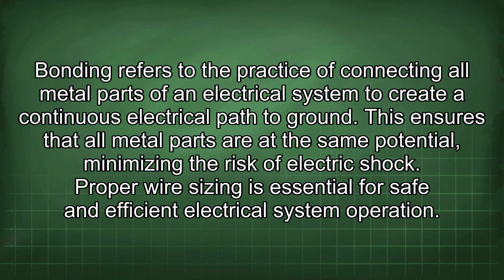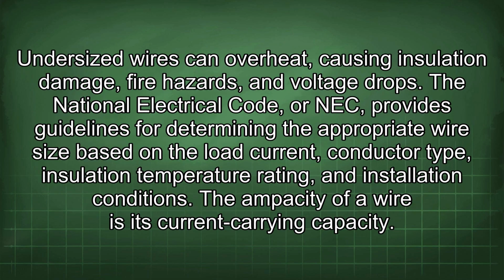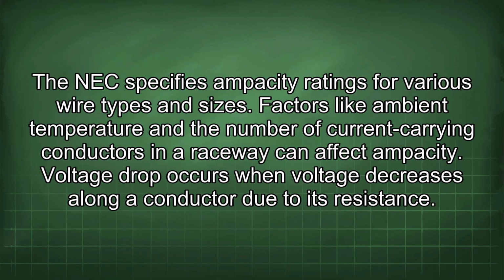Proper wire sizing is essential for safe and efficient electrical system operation. Undersized wires can overheat, causing insulation damage, fire hazards, and voltage drops. The National Electrical Code, or NEC, provides guidelines for determining the appropriate wire size based on the load current, conductor type, insulation temperature rating, and installation conditions. The ampacity of a wire is its current carrying capacity. The NEC specifies ampacity ratings for various wire types and sizes. Factors like ambient temperature and the number of current carrying conductors in a raceway can affect ampacity.